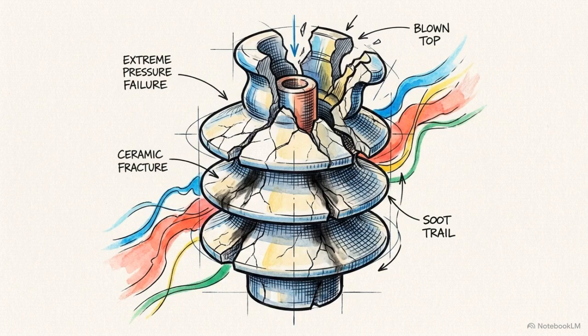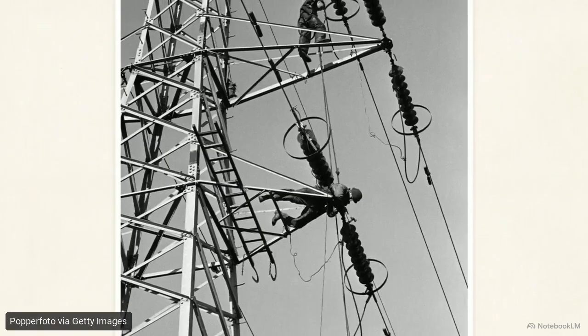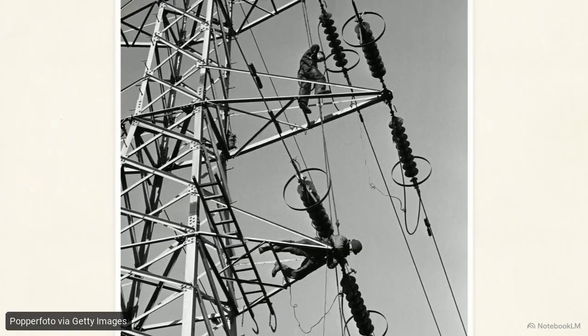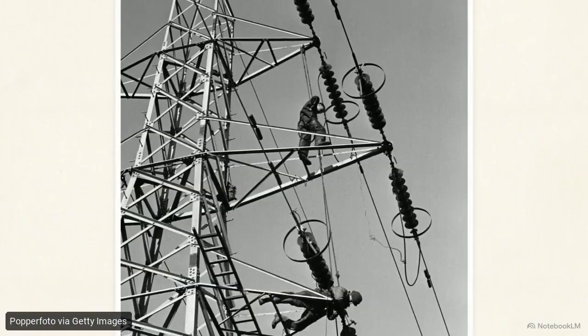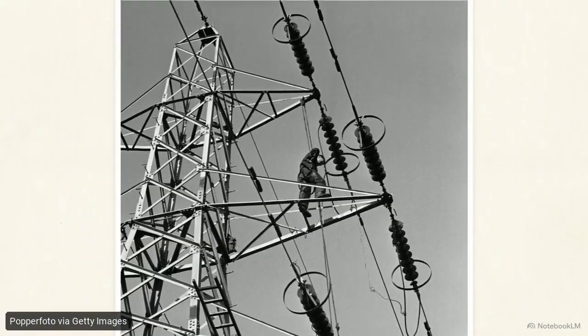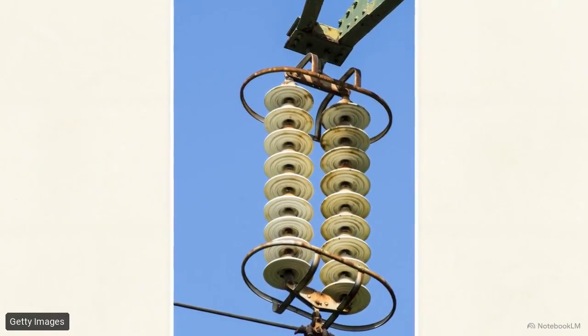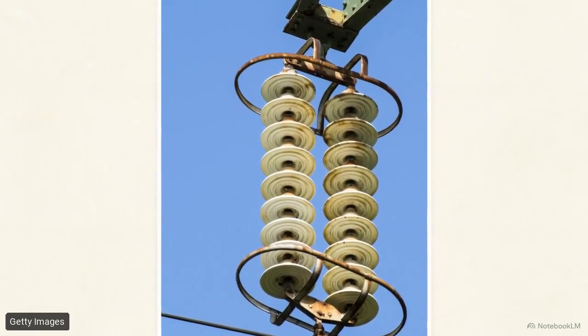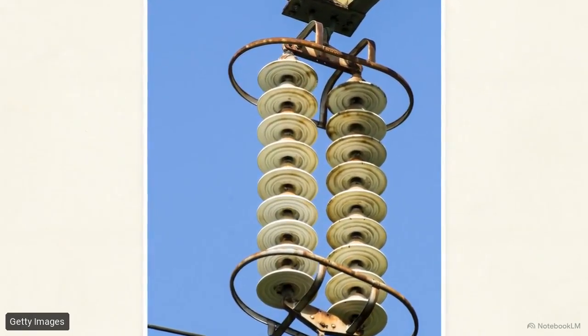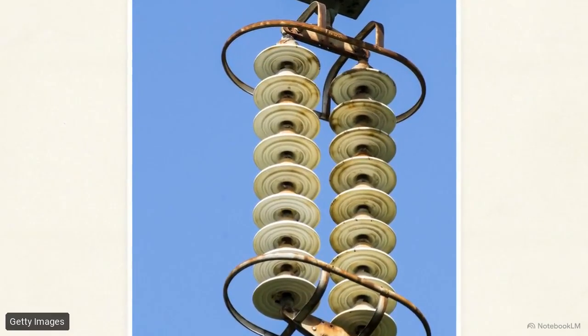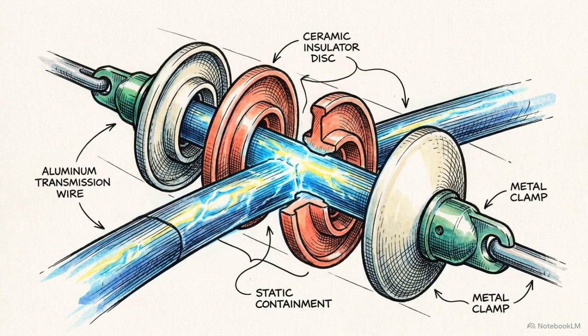Pin insulators manage distribution lines up to 33,000 volts. Beyond that threshold, the electrical pressure will punch through the porcelain or flash over the edges. For voltages like the 132 kilovolt lines on these towering lattice structures, engineers transition to suspension insulators. By stringing multiple ceramic discs together, they build modular strings capable of handling immense mechanical tension and holding back massive electrical forces. These porcelain barriers successfully trap the power inside the wire, but they cannot stop the invisible forces degrading the power as it flows toward the consumer.